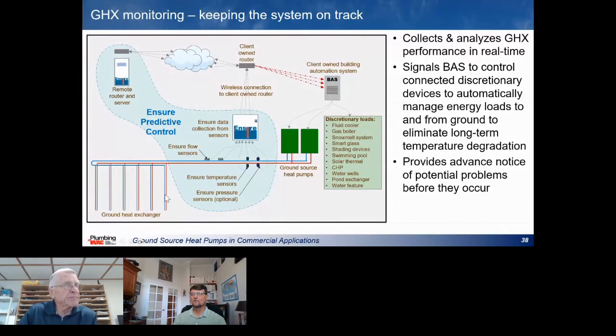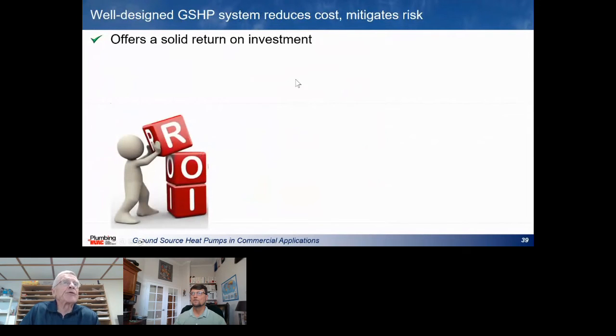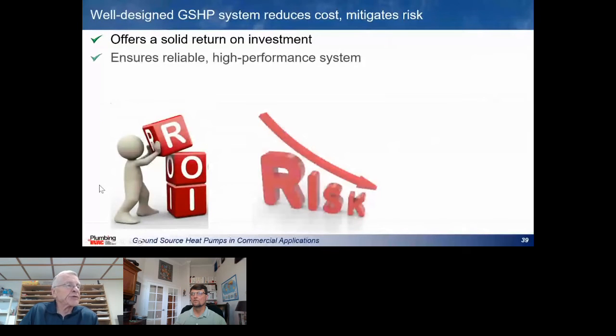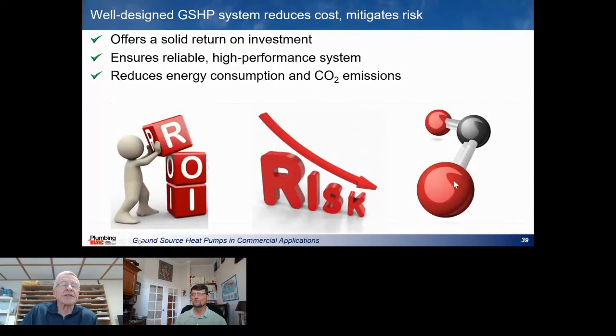And you can be sure that the electric and gas utilities are monitoring how much energy is being used from their system, and they're going to adjust the system accordingly. You can do exactly the same thing with a ground heat exchanger. So what I'm suggesting is that if you are careful with the design of the system and analyzing what the energy needs are for that building, you're going to get a much better return on your investment. It's going to reduce or eliminate the risk of operating that geothermal system. And you're still going to get the CO2 emissions reductions that the client and everybody seems to be looking for these days. And these things can work virtually anywhere.